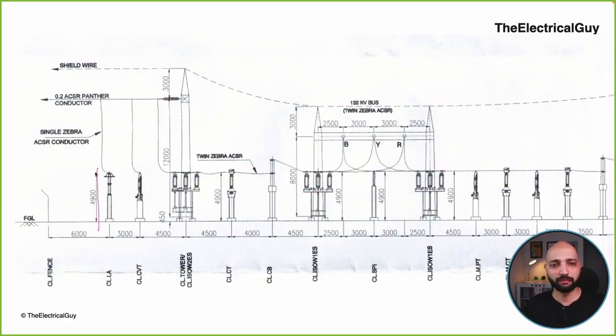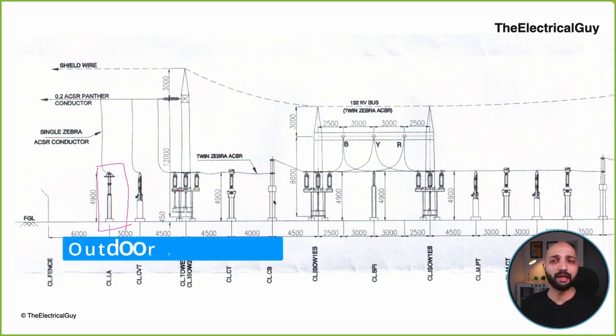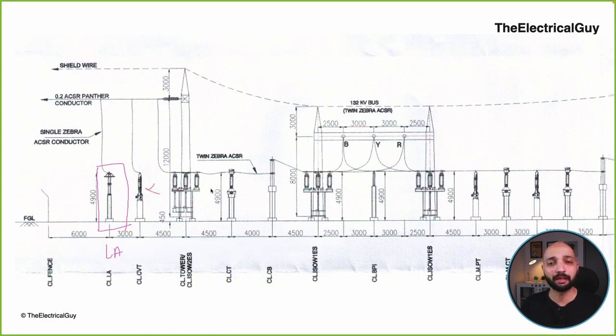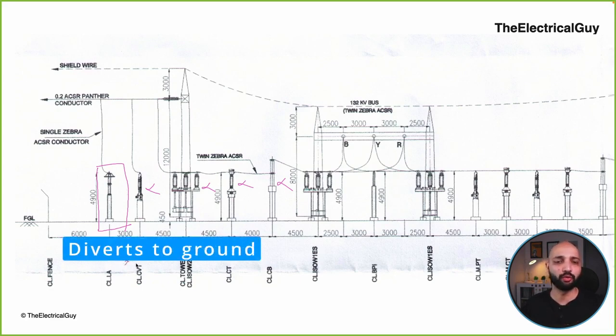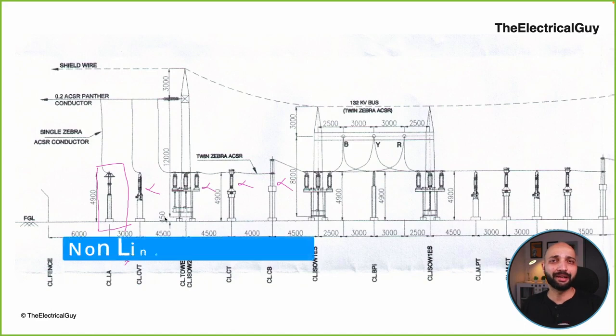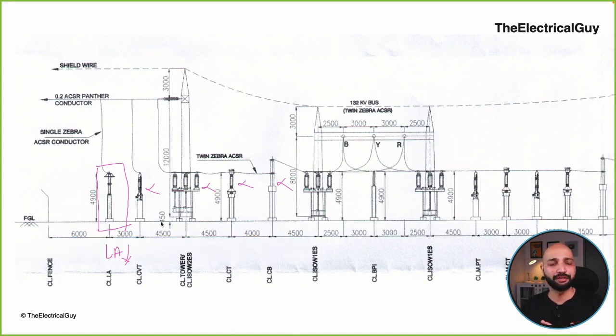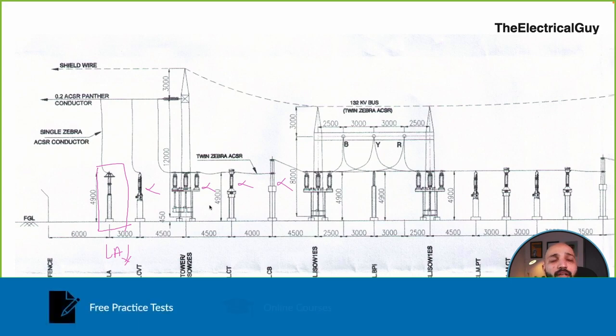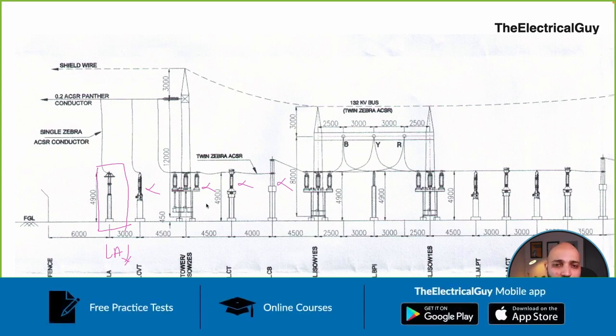So here is our first equipment, that is the lightning arrestor. The substation that you can see is an outdoor substation, and there is a possibility that in case of a lightning stroke, it can impact the equipment installed in the substation. In order to protect this equipment, we use a lightning arrestor, which diverts the lightning stroke to the ground. It is basically a non-linear resistance which offers a higher resistance for lower voltages, and a very minimum resistance as the voltage goes up. So that is one function of the lightning arrestor: it protects the equipment from lightning surges, right?